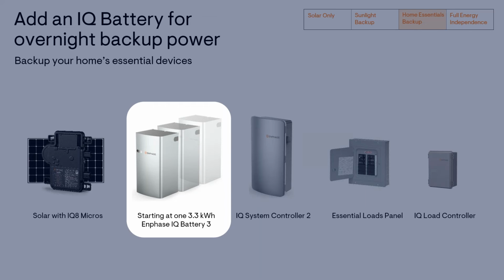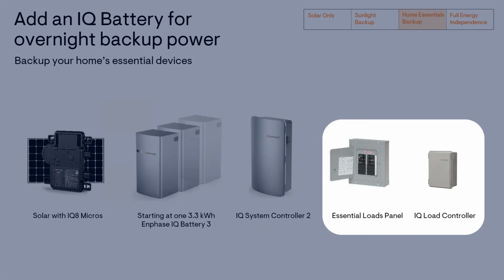Even though we now have a battery, we still highly recommend an essential loads panel. So the installer can designate which specific electrical loads are backed up by the battery and just select loads that the battery is capable of powering, as well as an IQ load controller to, again, be able to shed certain select loads which could potentially overload the battery or drain it very quickly.